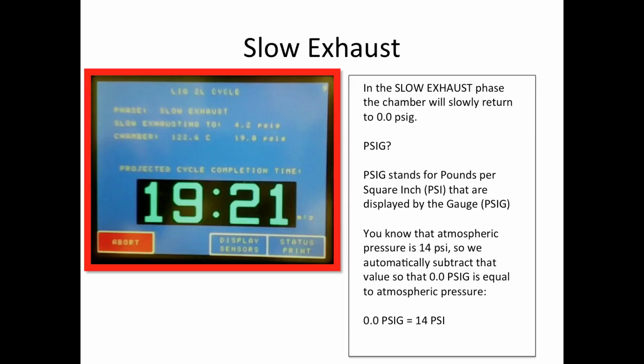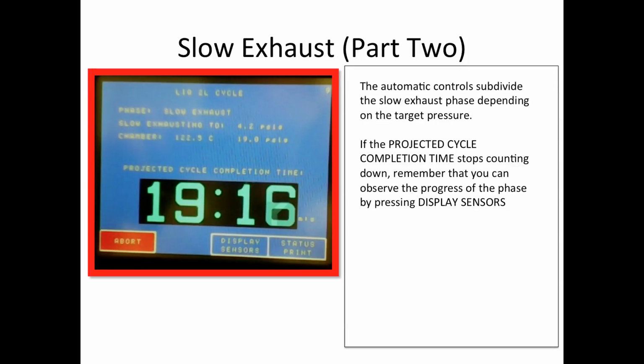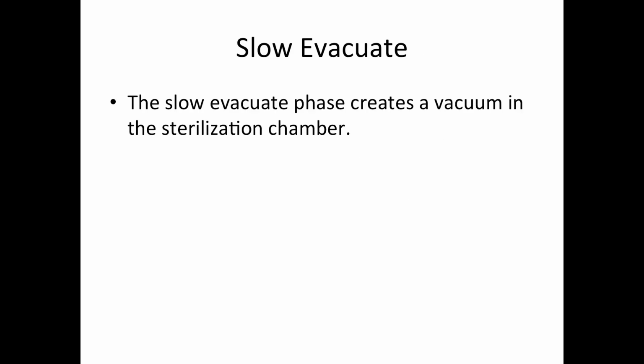You all know that the pressure of the atmosphere is 14 pounds per square inch. So that value is automatically subtracted from the value that is displayed on the gauge, or 0 psi gauge is equal to 14 psi. The automatic controls will have a second exhaust phase depending on the target pressure. Now, if the projected cycle completion time stops counting down, remember to press the display sensors button and see what's actually happening during this phase.